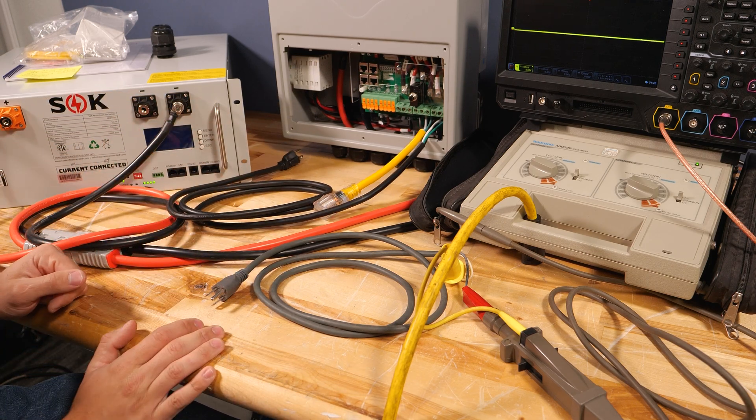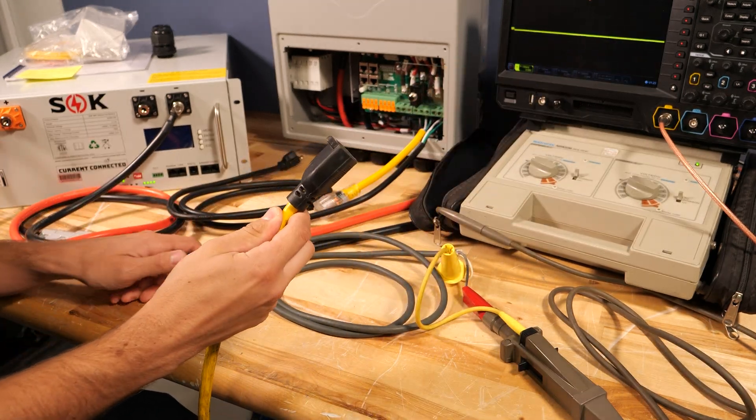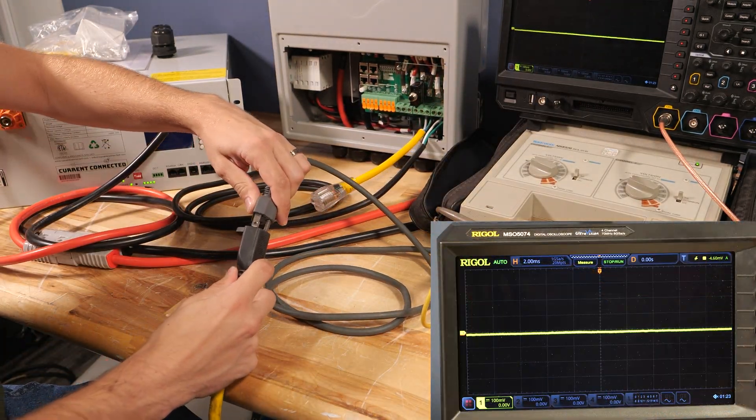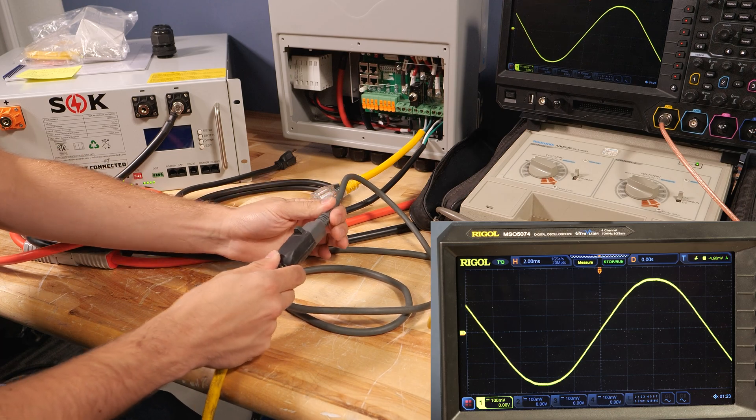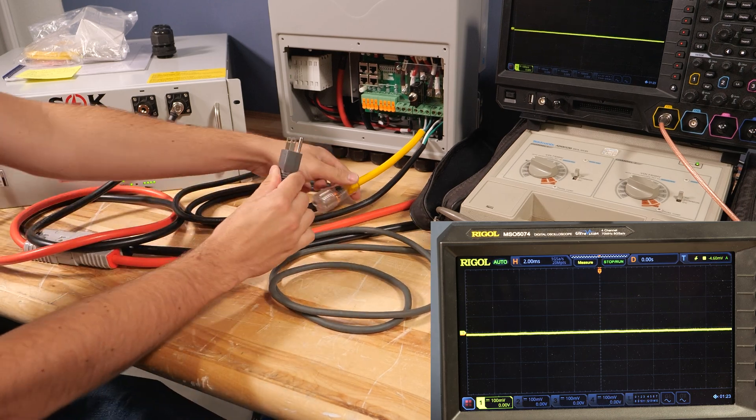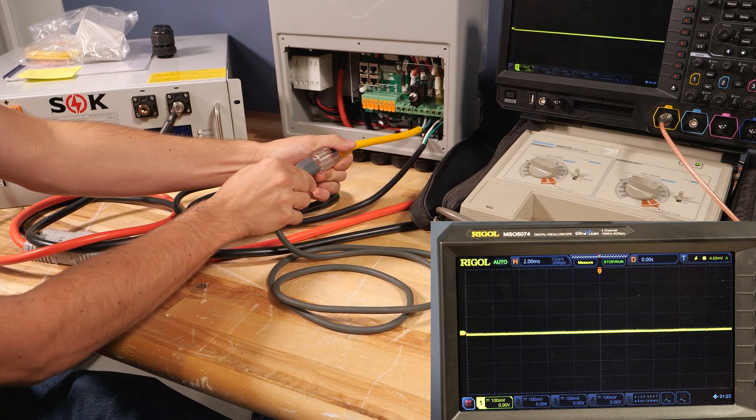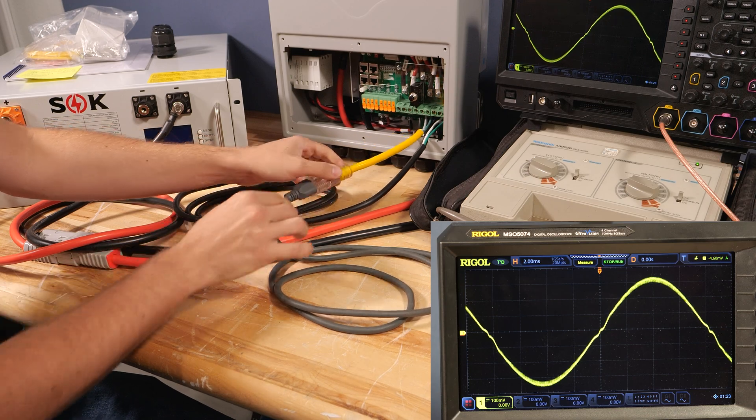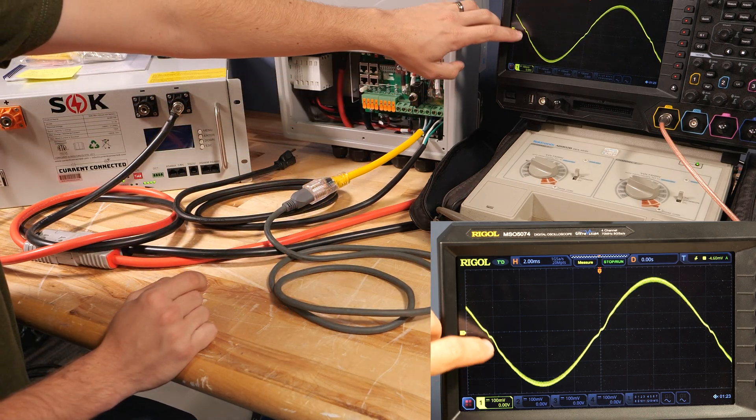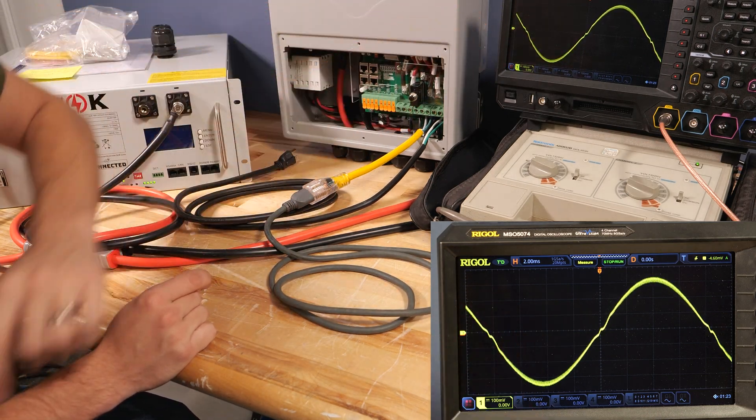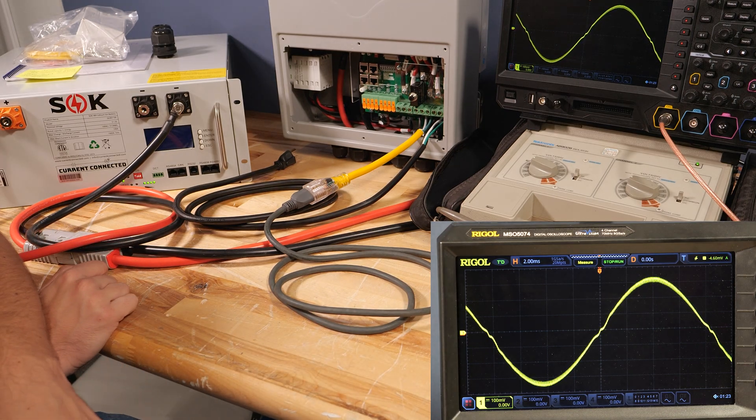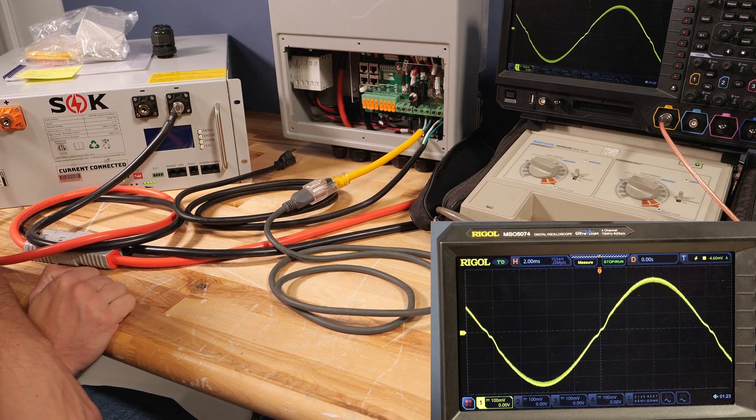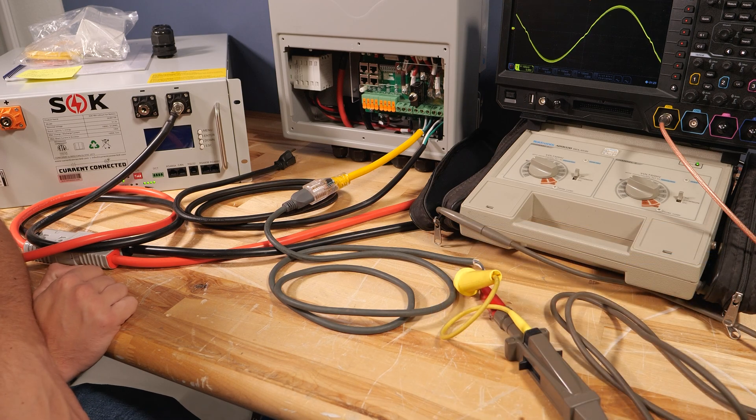So on this cord here I have grid power. If I plug into grid power you can see a nice clean sine wave. However if I switch over to the inverter it is still a real sine wave. However it is a little bit fuzzier. There are a couple of artifacts here but all in all this is still a true sine wave. It just has a little bit of noise on it. Not a big deal depending on what you're powering.